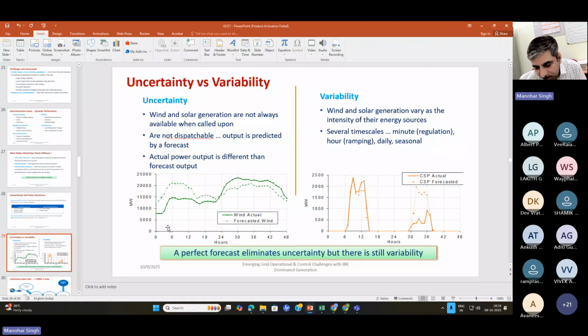Suppose I have a power system that is 50% thermal, 50% solar. When the solar goes down, I can't ramp up the thermal power plant fast enough, because its ramp rate is hardly 2% per minute—it takes an hour to ramp thermal generation from zero to maximum. By the time I do that, my system will go down. So the only option is to have fast ramping devices. My planning should be based on what I told earlier, but these are the operational issues I must take into consideration.